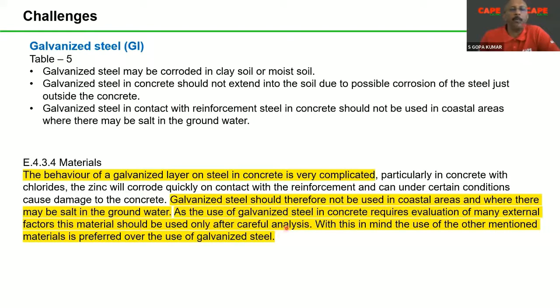But unfortunately, nowhere it is written what careful analysis. So it is very difficult to find out an answer for this careful analysis. The simple method is don't use it. With this in mind, the use of other mentioned material is preferred over the use of galvanized steel. The standard has recommended very clearly that GI, if you put it inside concrete, is having certain problem.